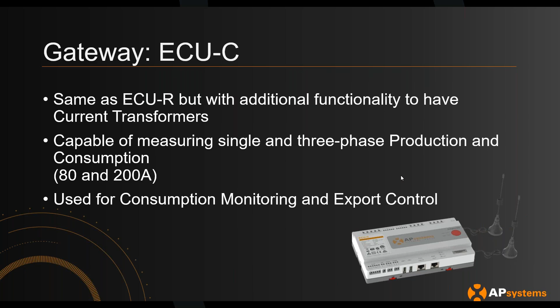One common request we get from customers is whether you can do consumption metering with external CTs. Prior to the AC combiner box, we often recommended using the ECU-C, which allows you to stick CTs into the unit for consumption metering. So it ends up looking something like this, with the consumption CTs plugged in here and the production CTs over here. One thing I like to remind installers is to make sure you're powering both L1 and L2 so you're measuring both phases.